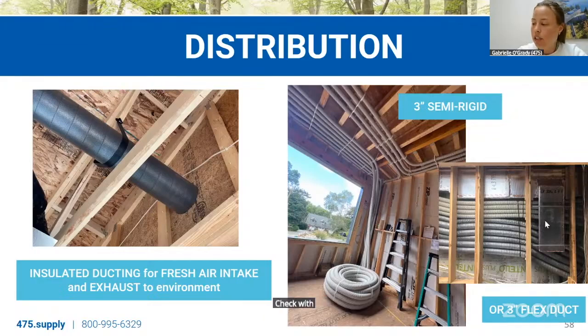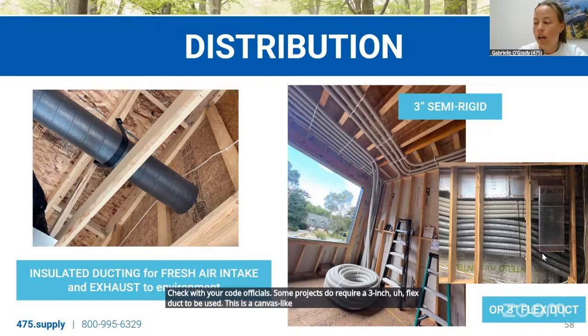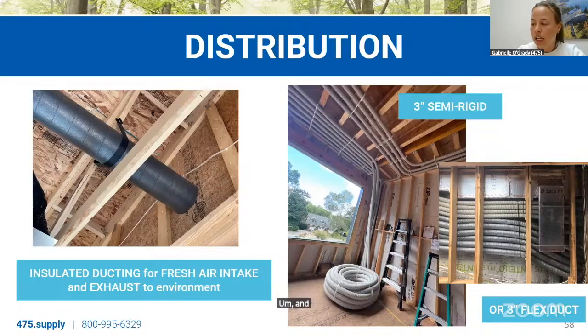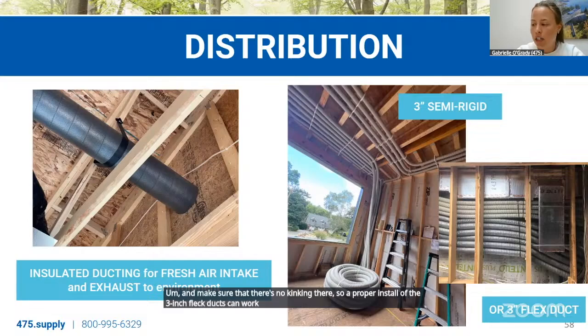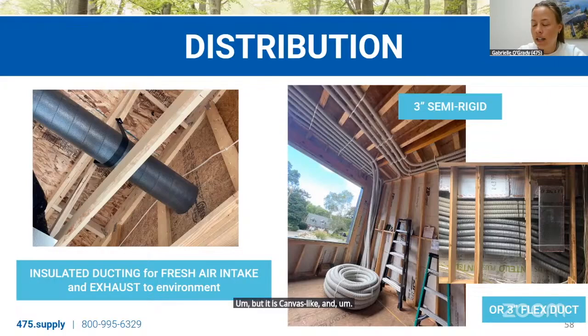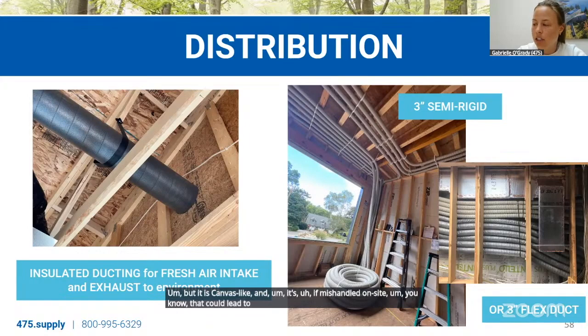Check with your code officials. Some projects do require a 3-inch flex duct to be used. This is a canvas-like material, and that's going to be UL rated. That can also provide excellent airflows when installed properly and when pulled taut. And make sure that there's no kinking there. So a proper install of the 3-inch flex ducts can work very well for projects, but it is canvas-like, and if mishandled on site, that could lead to tearing or damage to the ducts. So proper storage on site is also key.